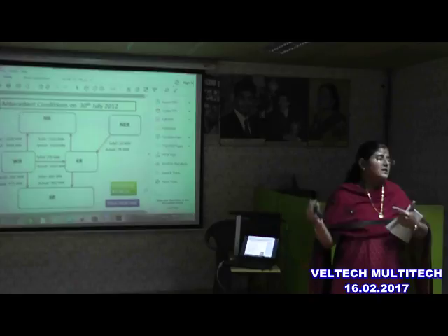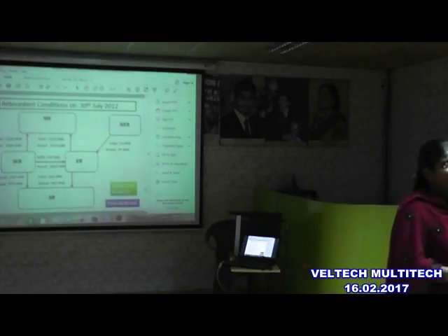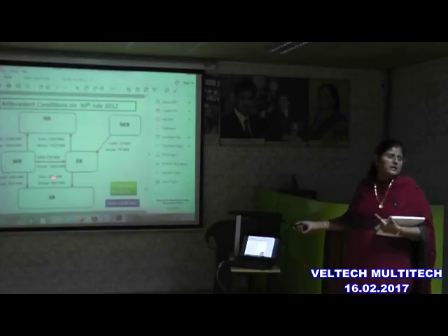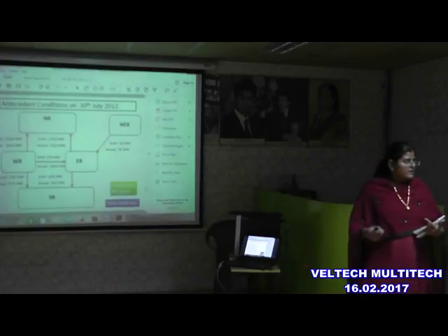In the sense, the operator was thinking it's a 765 line, and on paper it was a 765 line, but in actual it was a 400 kV line. So definitely overdrawing was taking place in the line, and it got disconnected. When one got disconnected, this was still able to feed ER till the next day. Then the next day, what happened? The problem aggravated, right? Again the same situation happened to western region.